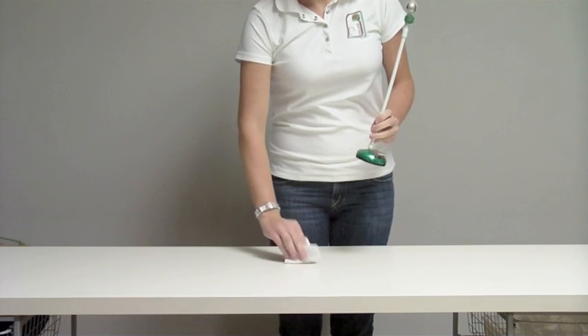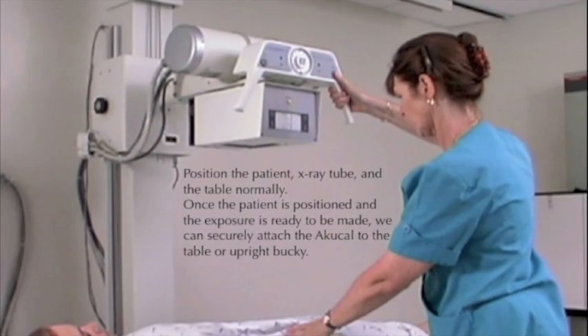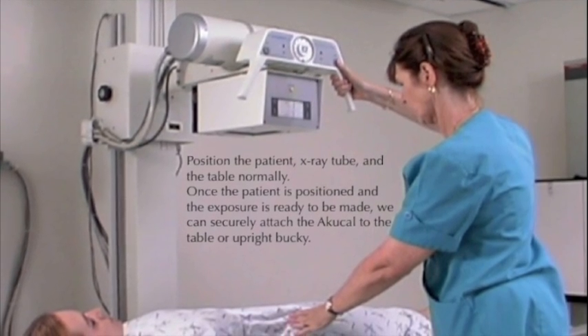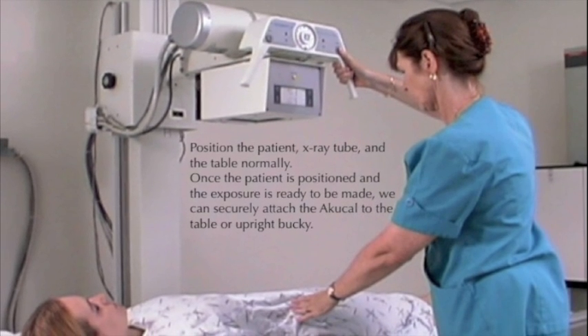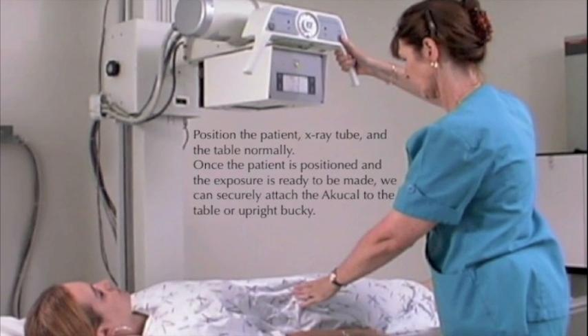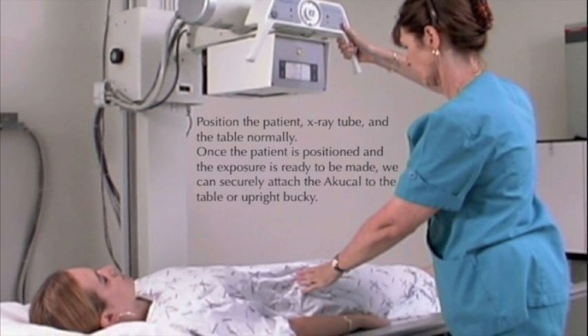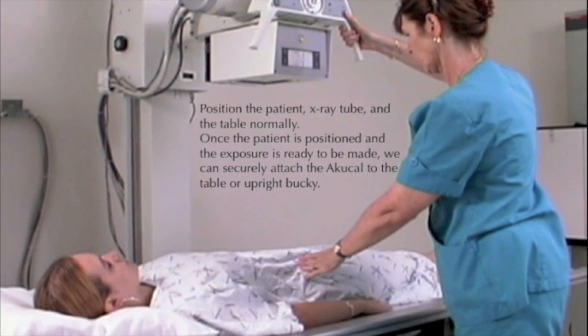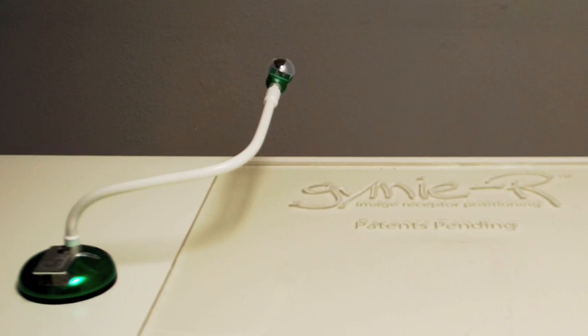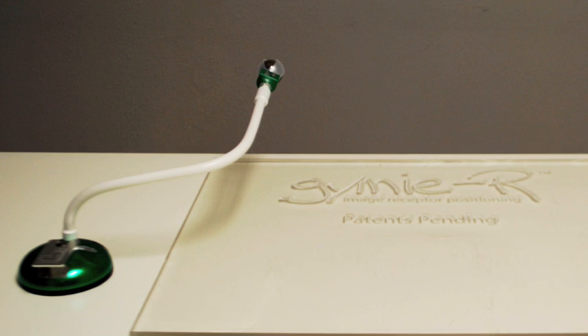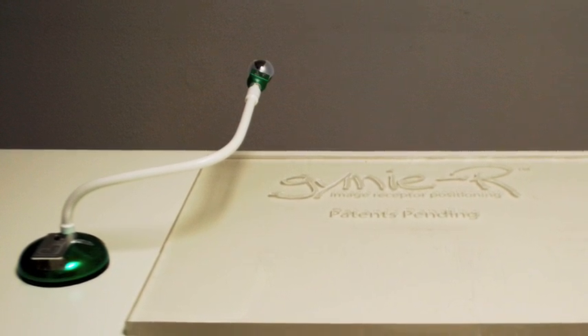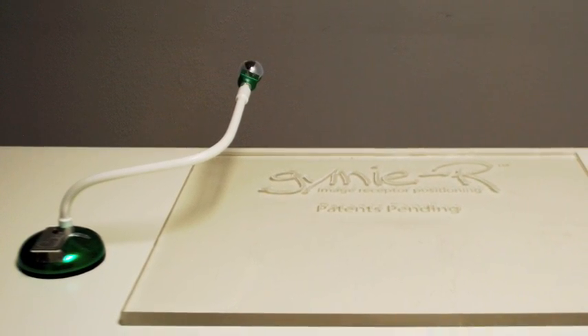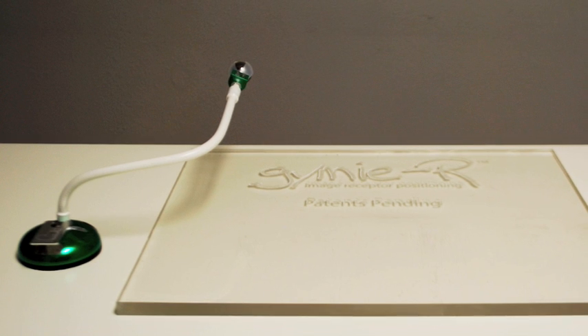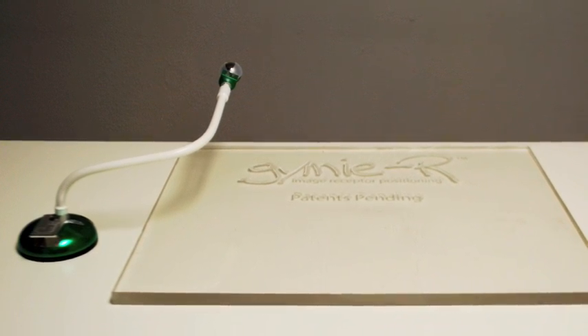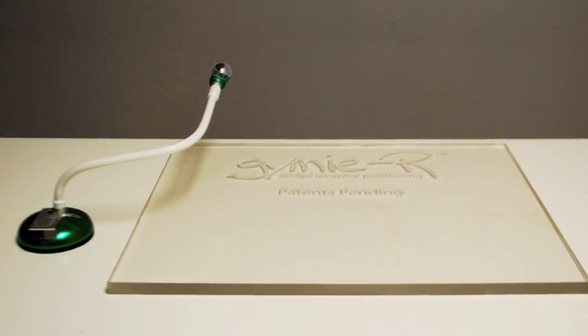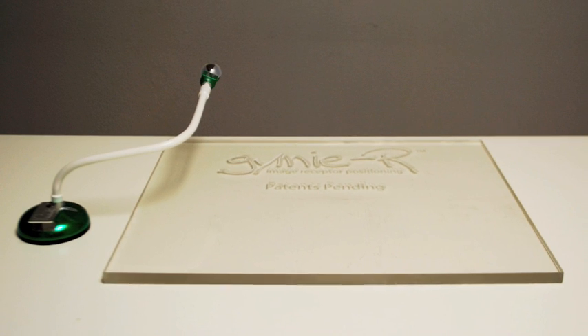to remove any dust or debris before attachment. Position the patient, X-ray tube, and table normally. Once the patient is positioned and the exposure is ready to be made, we can securely attach the Akucal to the table or upright bucky. Place the base of the Akucal outside of the field of view. Extend the Akucal's radiolucent arm into the field of view, placing the sphere next to the area of interest at bone level. Verify that the entirety of the sphere will be visualized on the captured radiograph.